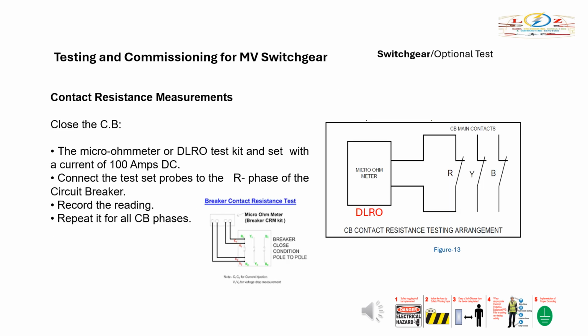7.5.3.1.11.2. Contact resistance measurements. Close the circuit breaker, and set the micro-ohmmeter or DLRO test kit with a current of 100 amps DC. Connect the test probes to the R phase of the circuit breaker. Record the reading. Repeat it for all CB phases.